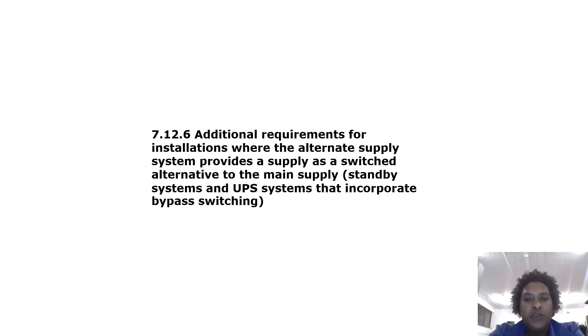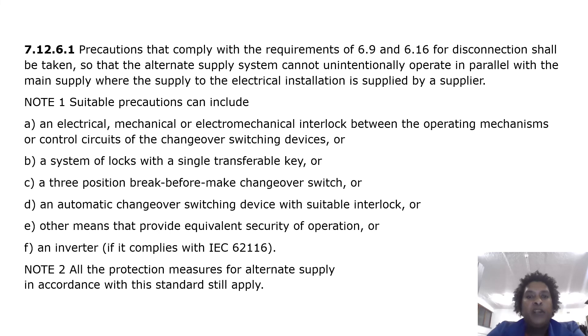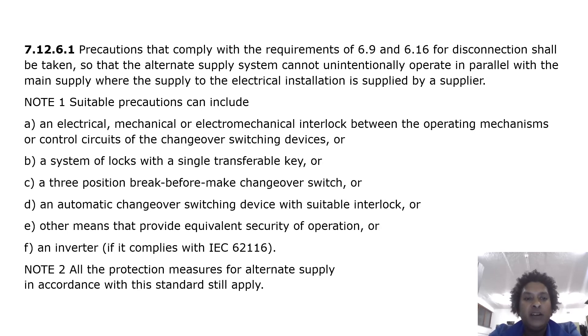Additional requirements for installations where the alternate supply system provides a supply as a switched alternative to the main supply, including standby systems and UPS systems that incorporate bypass switching: precautions complying with the requirements of 6.9 and 6.16 for disconnection shall be taken so that the alternate supply system cannot unintentionally operate in parallel with the main supply. Suitable precautions can include an electrical, mechanical or electromechanical interlock between the operating mechanisms or control circuits of the changeover switching device, or a system of locks with a single transferable key.